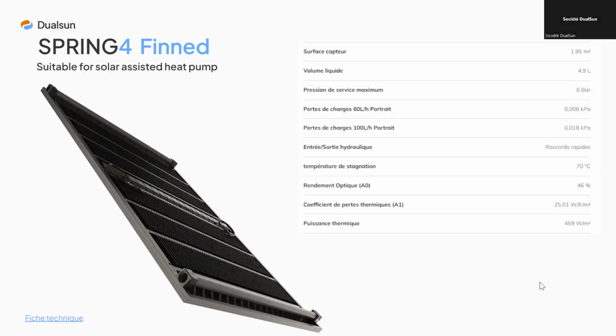We now see the thermal characteristics of the panel. We can talk about the maximum operating pressure, which is 6 bars, a very important factor and much higher than that of the previous version, the Spring 3. This high pressure maintains the constant pressure required for the heat pump to operate. Another important factor is the stagnation temperature, which is 70 degrees, which is the maximum temperature that can be reached when there is no longer any need for heating or domestic hot water, and when it's very hot during the day and the water remains stagnant inside the aluminum profiles. This eliminates any risk of polymerization, or we can also say caramelization or vaporization of the water and glycol, and avoids the need for a self-draining system that would allow the heat to be evacuated to avoid damaging the heat exchanger.